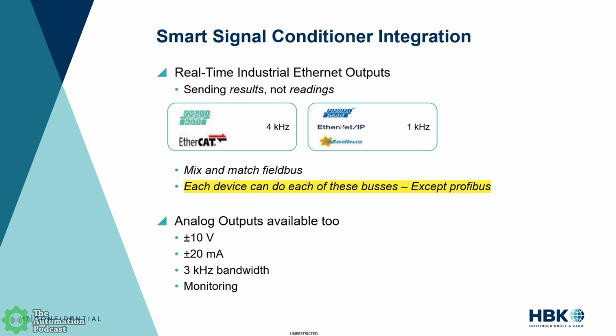These are great if you're retrofitting these into an older system that needed control level signals as opposed to digital communications. But they're also great for proximal monitoring, right? Maybe you need to feed into a meter because you need to go and actually see what the value is of the device at the device. These analog outputs are great for feeding into just a panel meter for that level of monitoring too. But whether you're using it for the actual signal or just monitoring, these devices have a lot of flexibility for how they can end up back in your system.